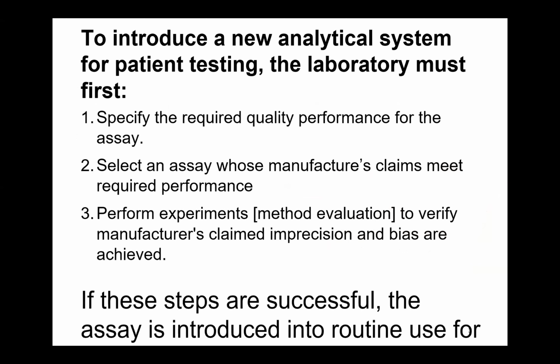Okay, so before any equipment is introduced in the system, before you start testing, before you start using the equipment, number one, the laboratory needs to specify the required quality performance for the assay, and then select an assay whose manufacturer claims meet the required performance. So you're saying we want an equipment that will perform these tests, and then you check which equipment can conduct the test that you're looking for. And then before you can start running patient samples, the laboratory will need to verify or validate the equipment against the manufacturer's claims. If these are successful, then the lab can start using the equipment.